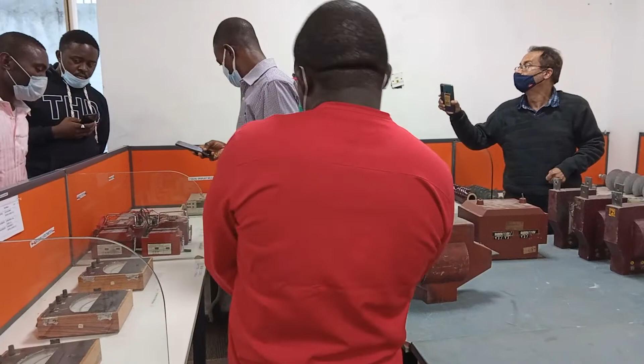And there are other protections. It is not only overcurrent, there are overvoltages also. If you ask the shopkeepers and shop owners what the price is, you will be surprised. The cost of an MCCB is double that of an MCB because of higher protection. You are not familiar with it till date. There is a higher level of protection under MCCB which is not covered under MCB. And I told you in the morning, if we case study it thoroughly, in any feeder protection in the country and the globe, there are major faults, which normally come in megaohms. Earth test never comes in megaohms. It is in ohms. Am I right? Yes. So that is the difference between earthing resistance and insulation resistance.